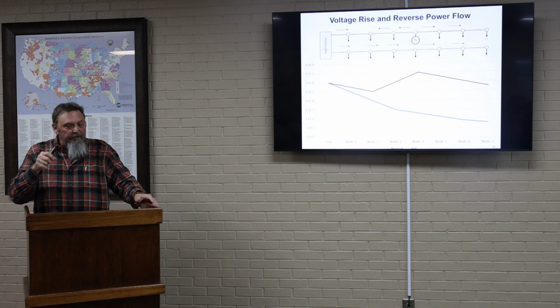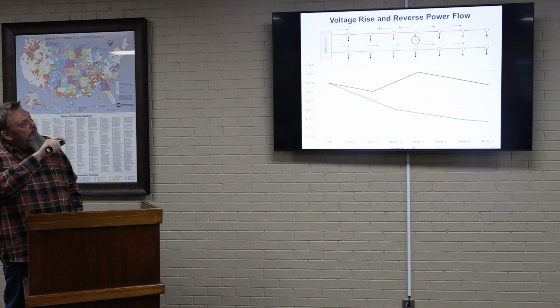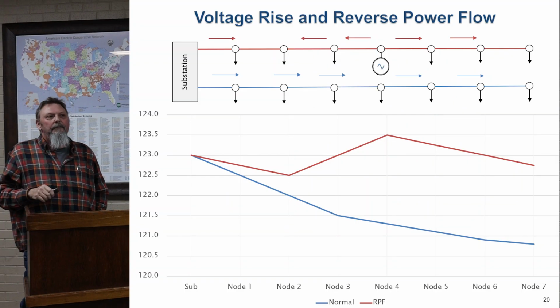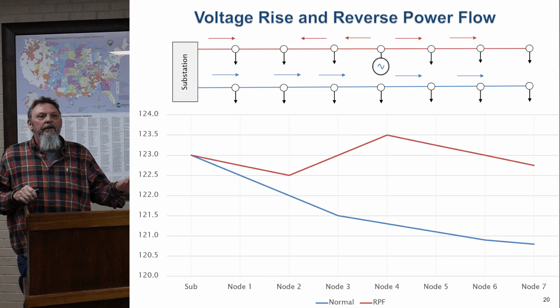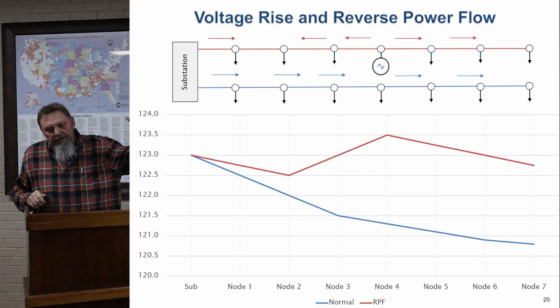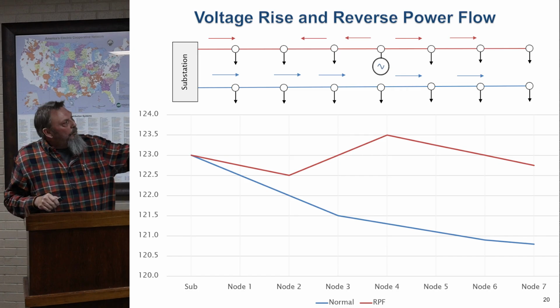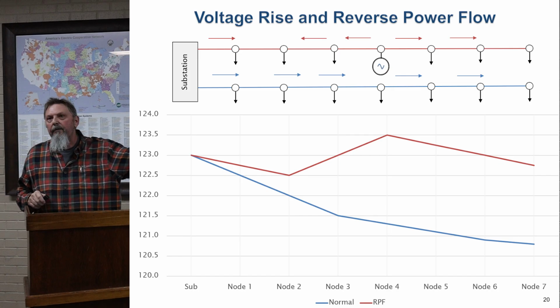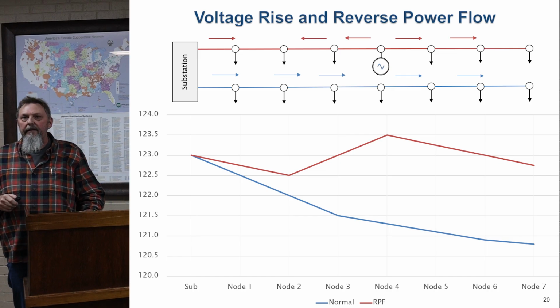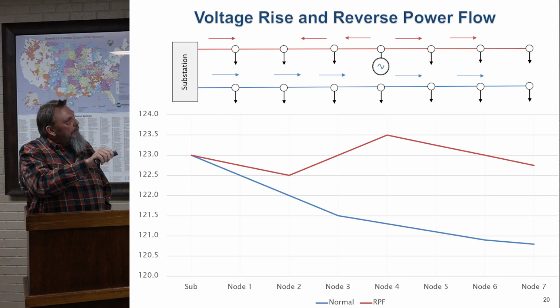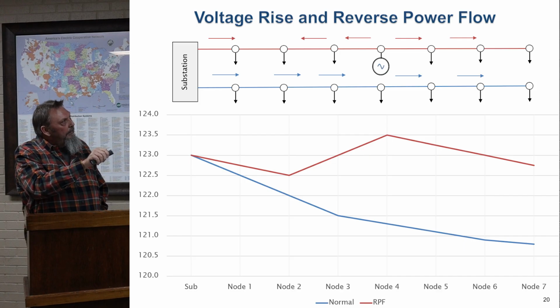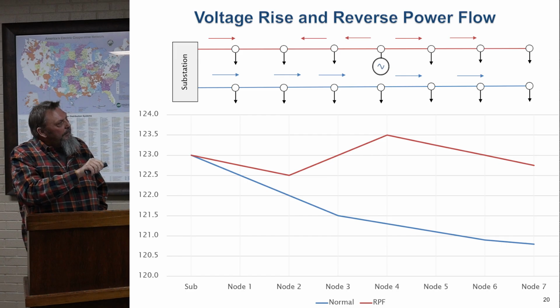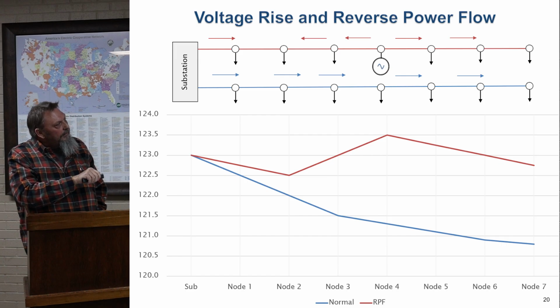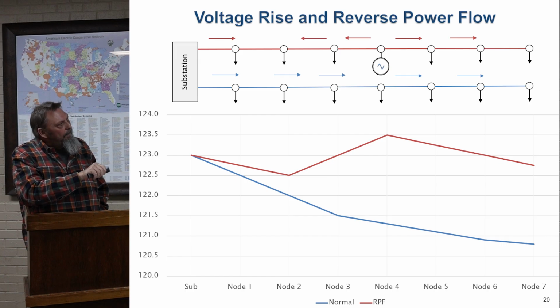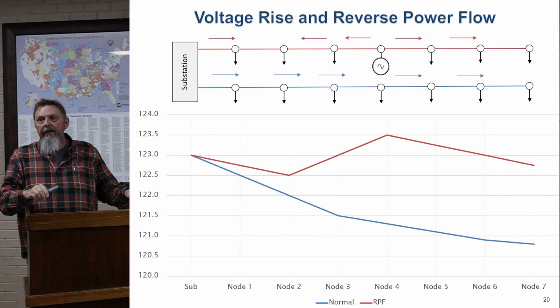So here's what I'm talking about — the substation, the blue line there, that's our traditional distribution line. We've operated this way for 100 years. We leave the substation, go out, it drops load, drops voltage — our voltage consistently goes down, and we know exactly what it is at the end. But when you put a generator in the middle of it, now you have power flowing in two different directions, and instead of your voltage going down like we anticipate, it starts going back up, and then it might start dropping back down again.